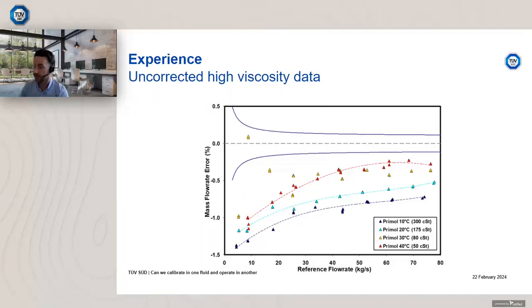And you can see here that near enough all the data is outside the manufacturer specification, apart from 2 rogue points down at nominally 10 kilograms a second with the 30 degree Primol data. That appears to be inside the manufacturer specification, but the rest isn't. Now I often get asked what's the issue here, and it's simply a known effect with Coriolis meters, certainly of certain geometry anyway, and that is a Reynolds number effect.